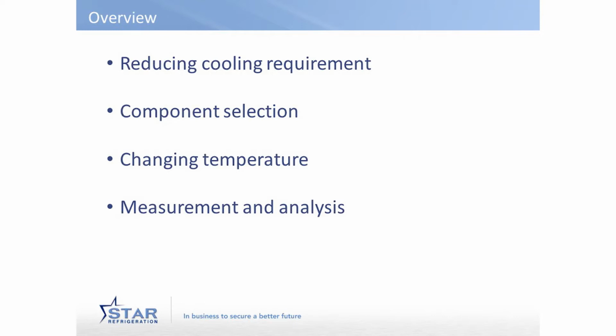And then finally, measurement and analysis of the system to make sure, this is one of my real bugbears, my pet hates, make sure that it's still operating next year and the year after and 10 years after as well as it was operating when it was new. And it's incredible the number of systems that never get checked. They get put in brand new and they're operating, but nobody ever goes back to see is it still running in the way that it's supposed to be running. So there's a lot of benefit that can be gained just by having the ability to do that exercise.